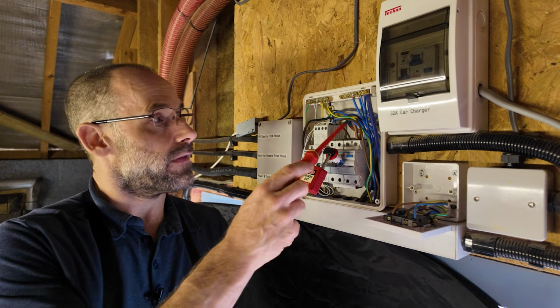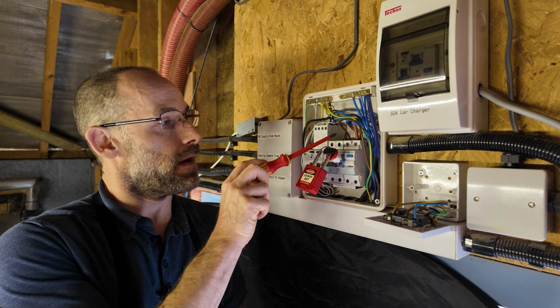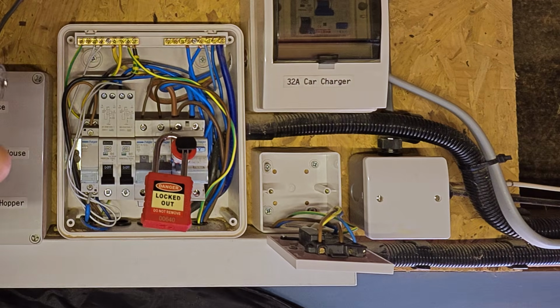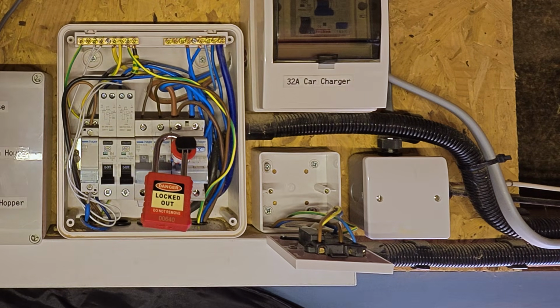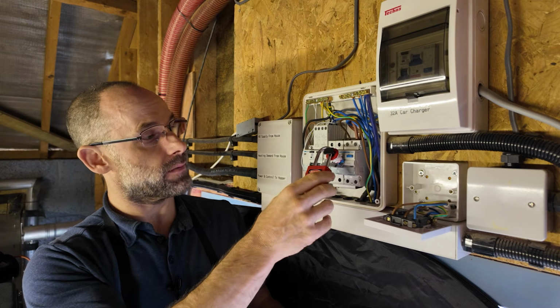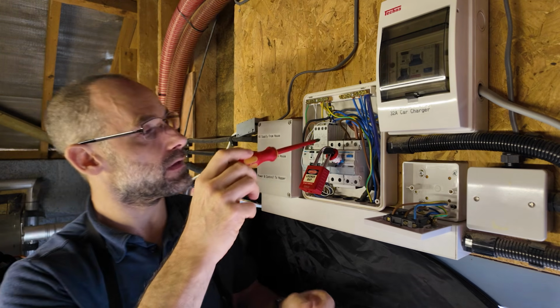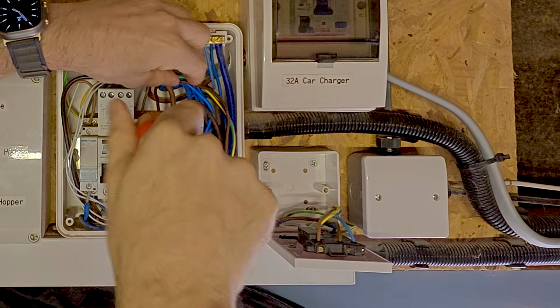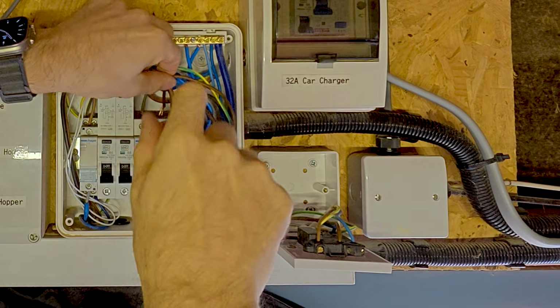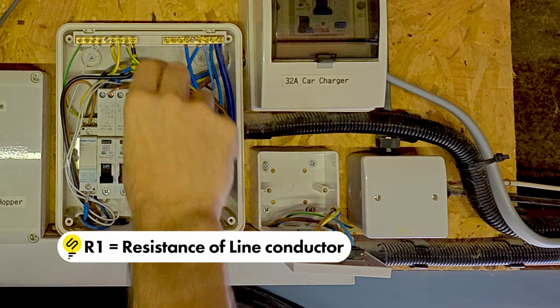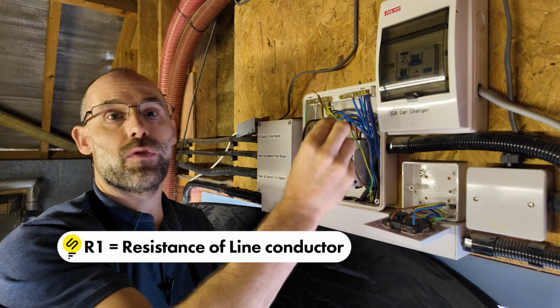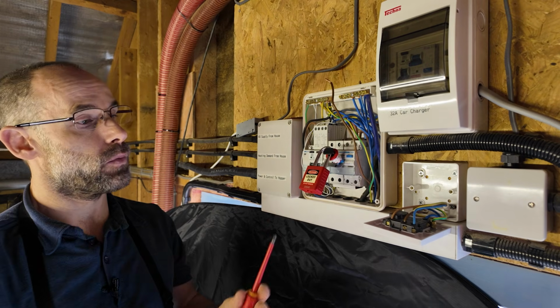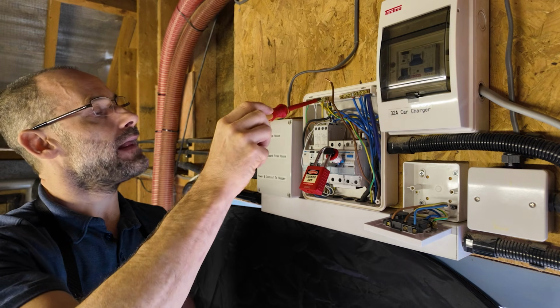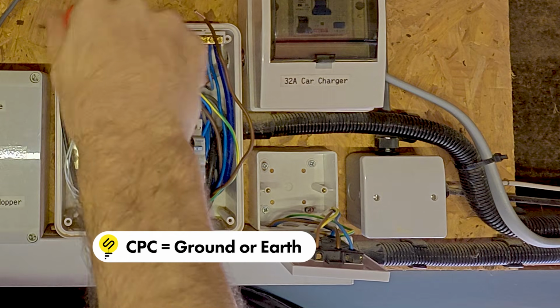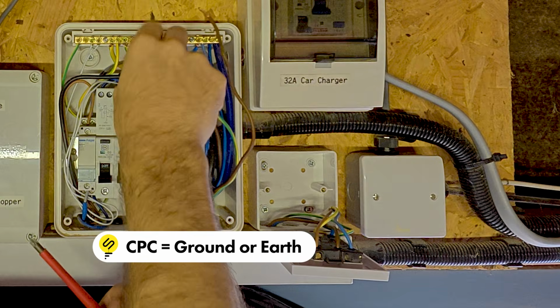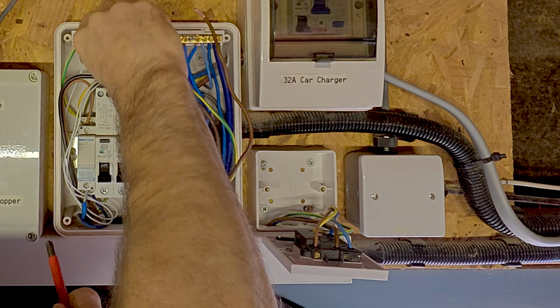So step one is to test that the wires that connect from the circuit breaker here to the fused connection unit have complete integrity, they have continuity. So to do that, obviously, firstly, we need to be completely locked off and isolated for safety. And then what we're going to do is disconnect the cable here, and this is what we call in the electrician trade R1, resistance 1 for the line conductor. And we want to test the continuity between that and the CPC, which is otherwise known as ground or earth, the circuit protective conductor, which is this guy here.